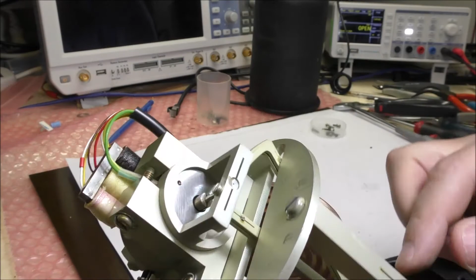So we have an LVDT sensor with one excitation coil, so we have a brown terminal and a red terminal. And we have two measurement coils, connected in series. These are the two yellow wires here. And then we have the white wires. So we have one white with a red tube here.